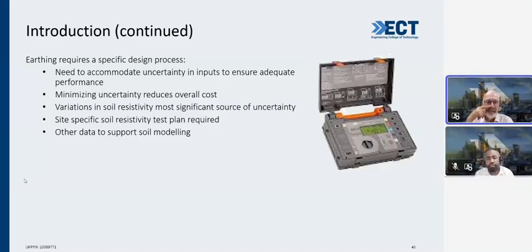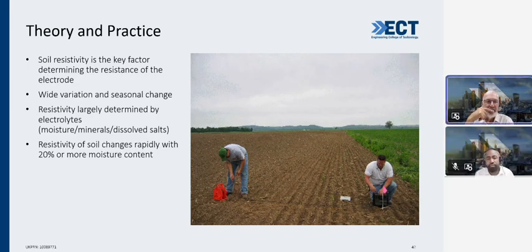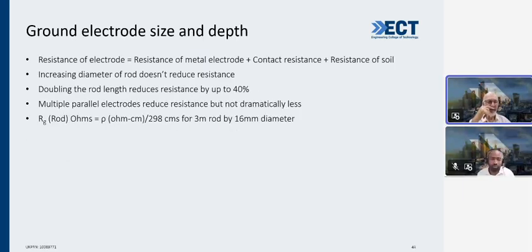Next slide. So soil resistivity is a key factor. One of the challenges is measuring it, because when you put an earth rod into the ground, you want the resistance to be as low as possible. But if the ground is wet, it'll have a low resistivity, and in the middle of a drought, summer or winter, when there's no rain, it's dry again. So it is a challenge. Or if you try to put an earth rod in on a rock face, what's the resistivity going to be like? It can change quite dramatically, so one has to look at the worst-case scenario when doing this.